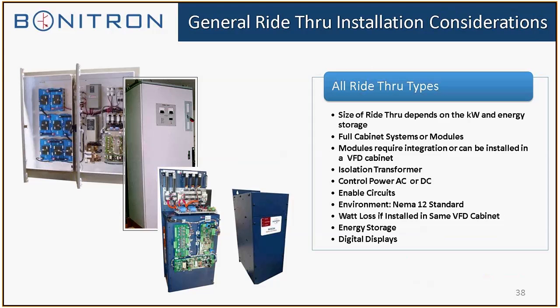And now some installation considerations for ride-through as a standard. This applies to all of the different ride-through types. The size of the ride-through is going to depend on the kilowatt rating required, which comes from your motor specification, what's required from the motor as far as holding it up during a ride-through event, and the energy storage. And we will put any kind of control power option in the same cabinet, AC or DC. Enable circuitry is in there.